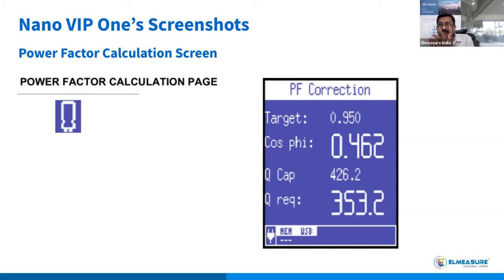So what is important is where my power factor is going wrong. Sometimes the power factor at the incomer will be around 0.98 or so, but when you go down the feeder line or near the motor end, the power factor will be very bad.